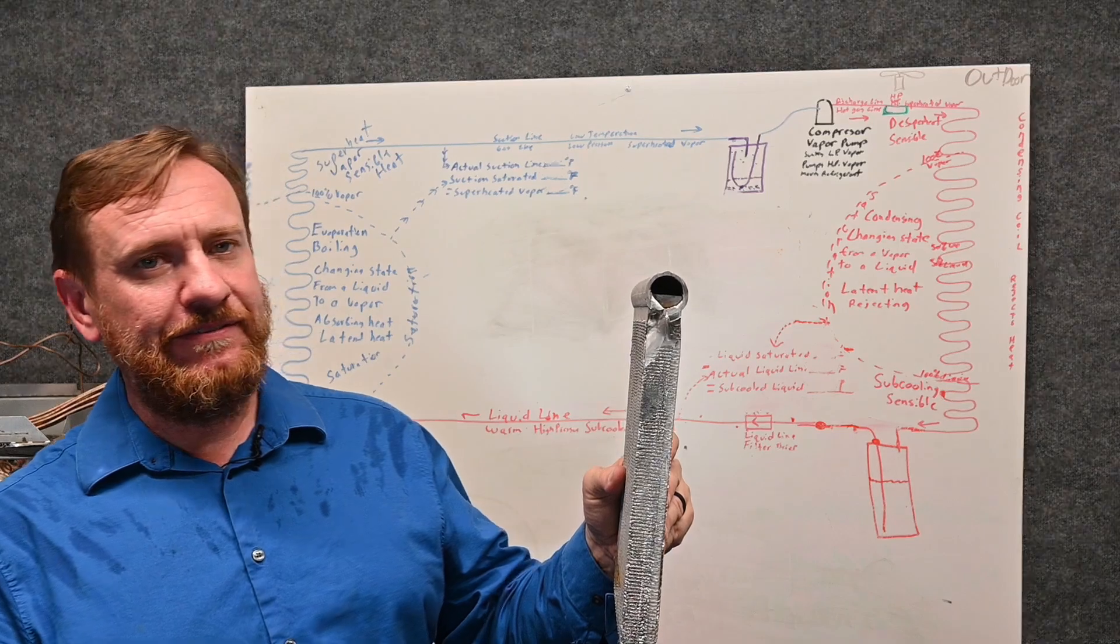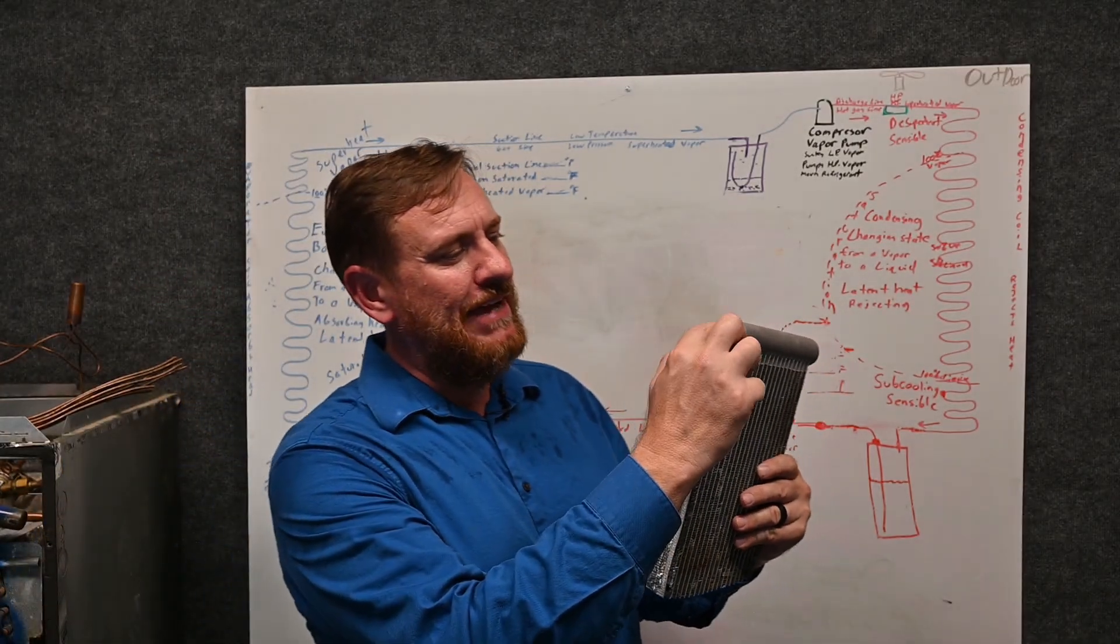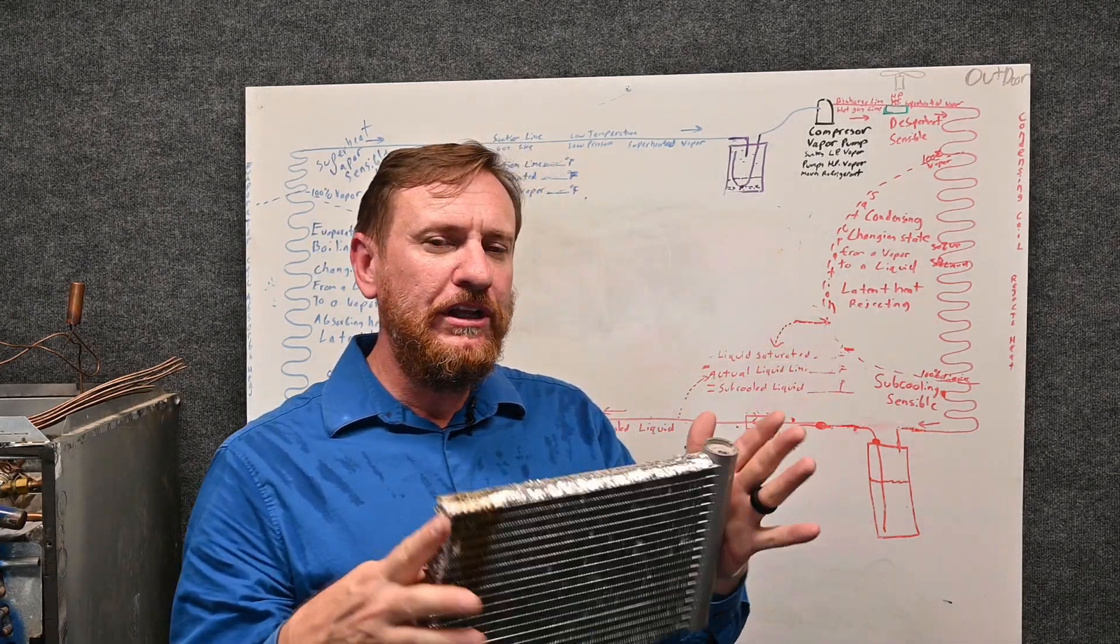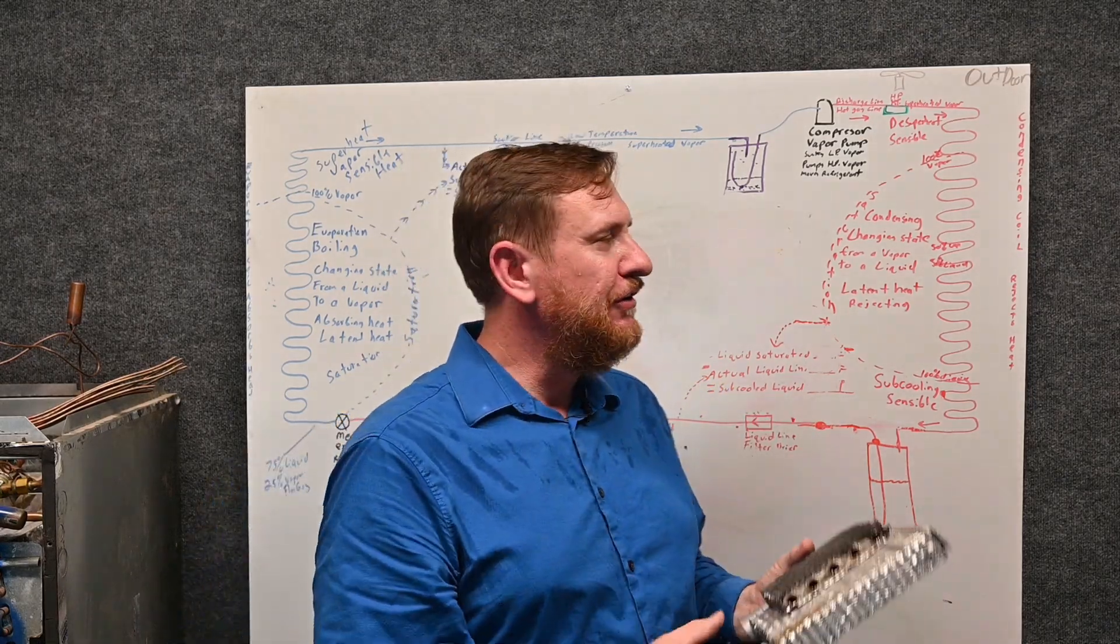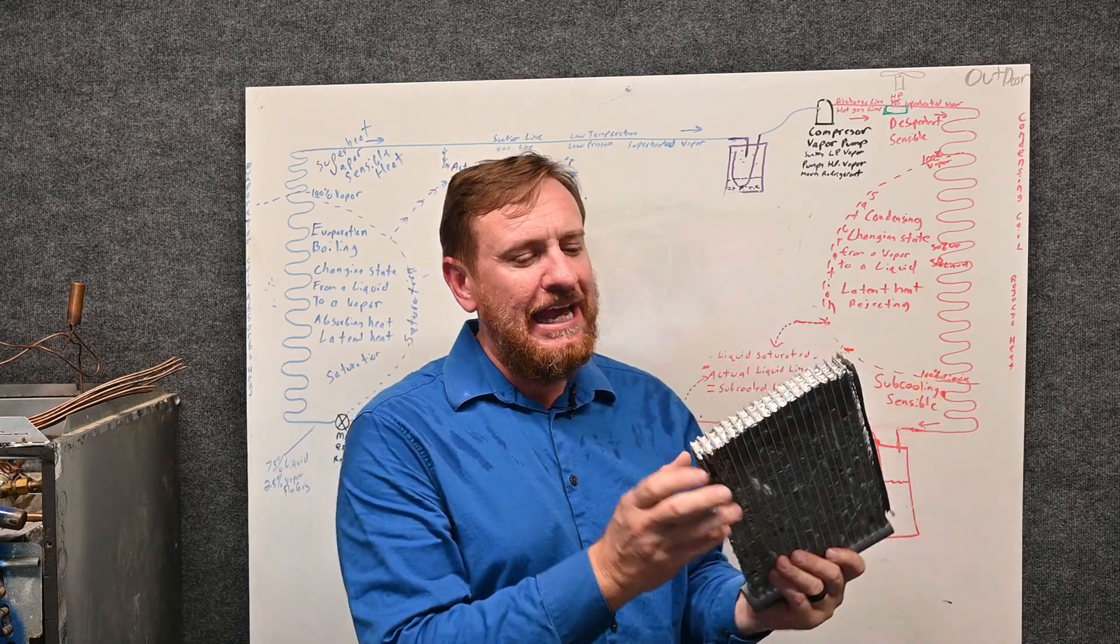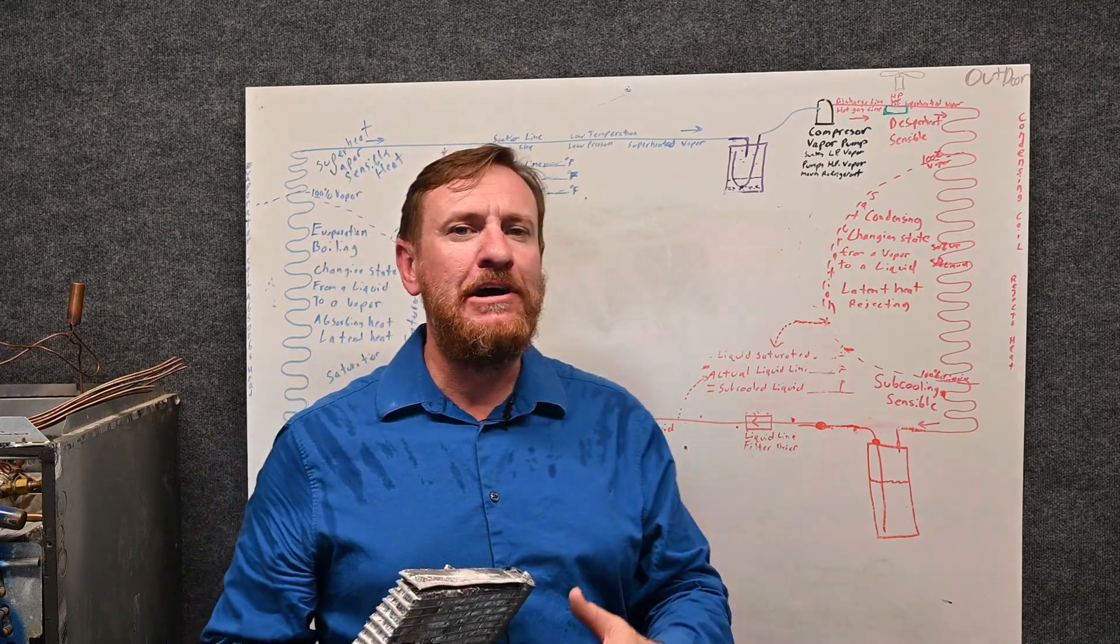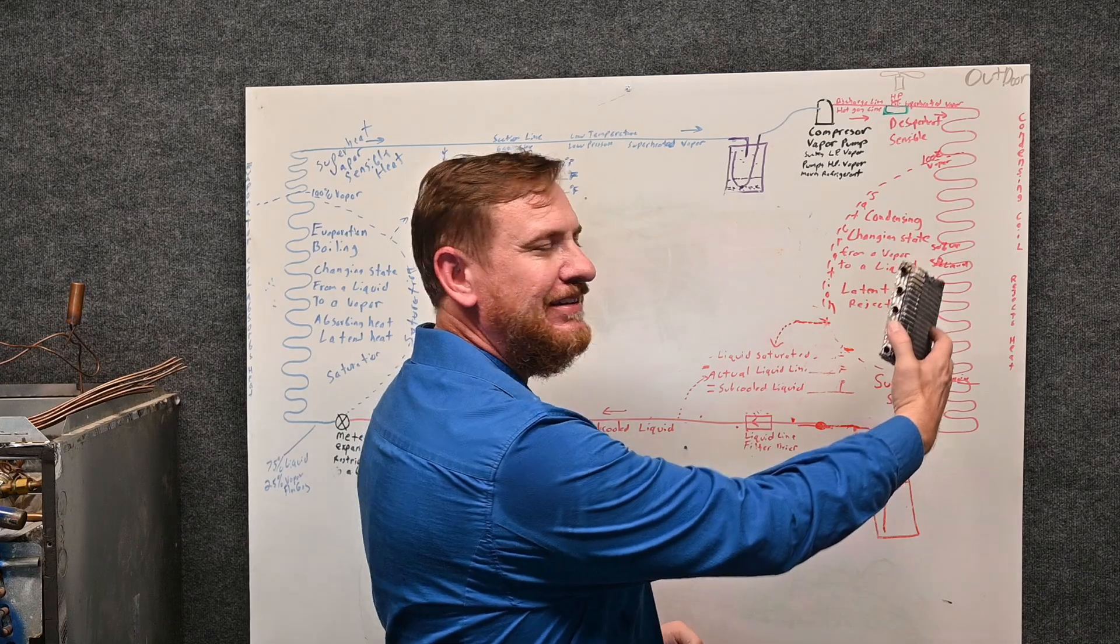We'll get to that part of the course later on. We'll look into the very end of this. You can see that we have a pipe and then all those little micro-channel pieces come in to the very end. So these work really, really great as far as heat transfer, but let's also think about another issue. Let's talk about the subcooling. Here we subcool into liquid. As small as these tubes are, they don't hold very much liquid. At some point in time, we're going to be talking about doing a pump down where we store liquid refrigerant inside of the condensing coil.